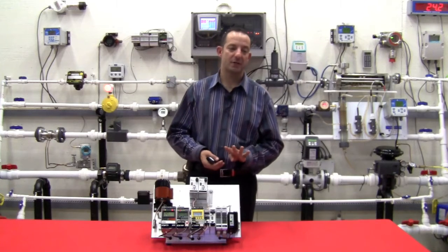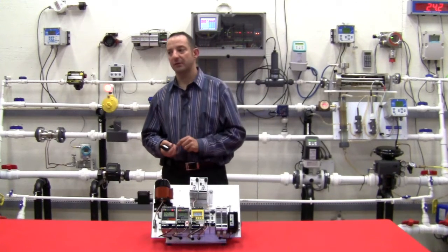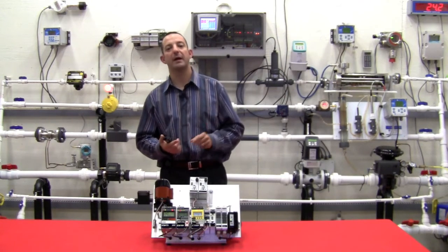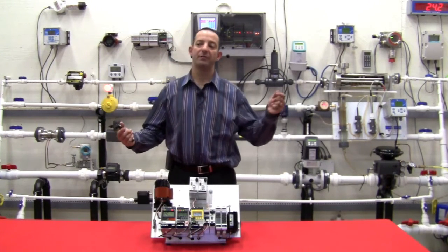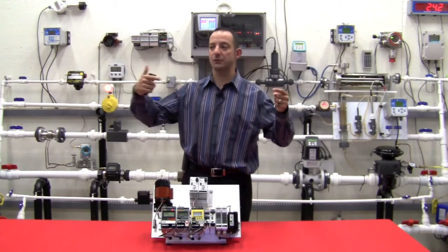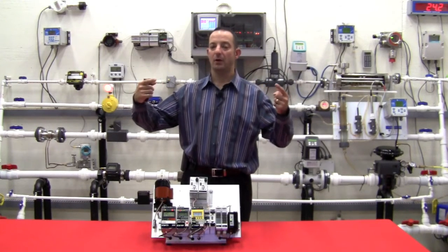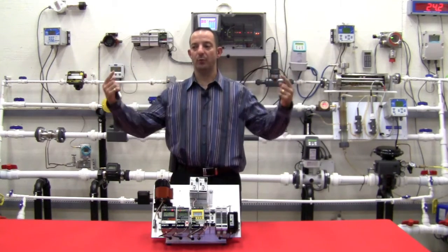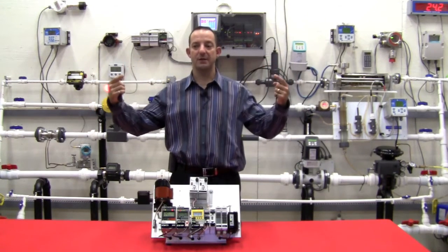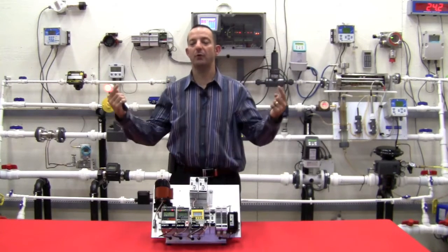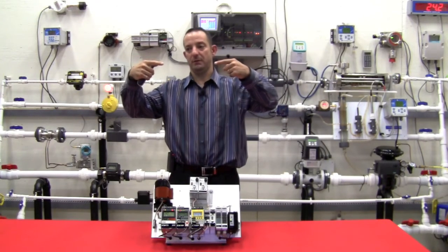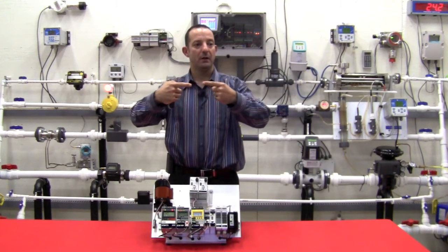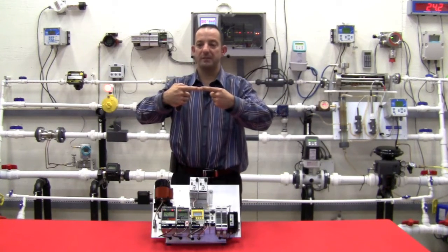The fourth application that you solve with isolators and converters is bucking power supplies. Bucking power supplies occur when both a field transmitter and the control system receiving that signal both try to excite the current loop with their own 24 volt supplies and drive current into each other. They both try to act as current sources. When you hook 2 current sources up together, we say the power supplies buck each other.